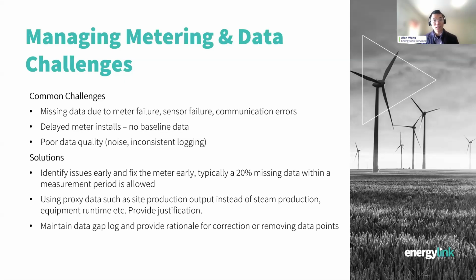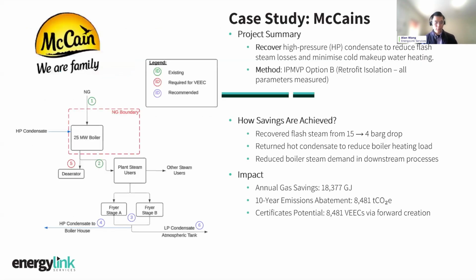So if we move on to the last slide, if we look at the real example, in this case McCain in Ballarat, they're in the process of implementing a project to recover high pressure condensate from their boiler system, which includes a 25 megawatt boiler. So it's actually quite sizable. The goal is to reduce flash steam losses and minimize the energy required to heat the cold makeup water.